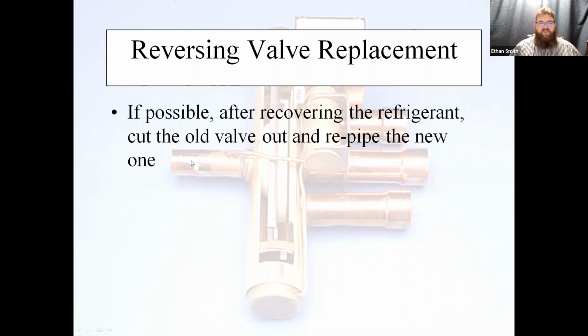The only point that I would say is pretty safe to unbraze is usually this discharge line, because that's about the only one that you're going to have play on. So you can usually unbraze this one, but these bottom three pipes, they're really miserable to unbraze at the same time. I've seen all sorts of funny solutions to this, guys with triple-headed torch tips. You can actually buy them now, with multiple tips that you can position to try and unbraze multiple lines at a time. It's a lot easier, guys, to cut the old valve out with a tubing cutter and then get some repair couplings that will slide up over the pipe, put it into position, push the coupling down into place, and then braze it.